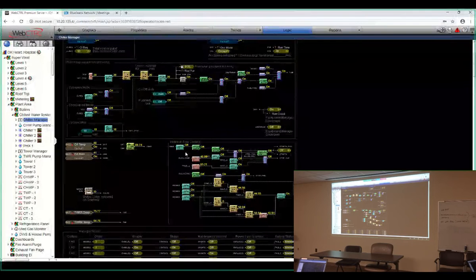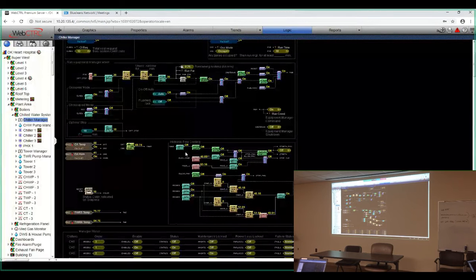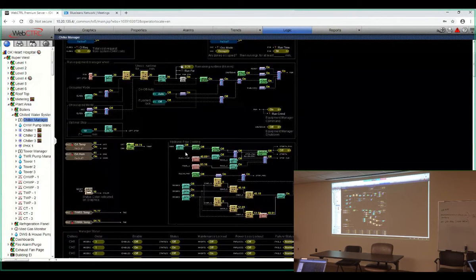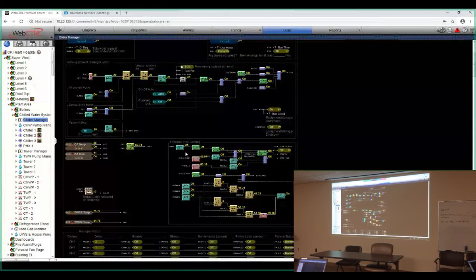And where's the data for the outside air temperature coming from? We do have a weather station, and we also do a couple of different things. We have a local sensor, and I make changes in the plant based on the local sensors. But all the reporting with targets comes from AccuWeather. I think it comes from Tinker Air Force Base. That only resets every hour, and that can get us in trouble in Oklahoma when we don't see the temperature but every hour.